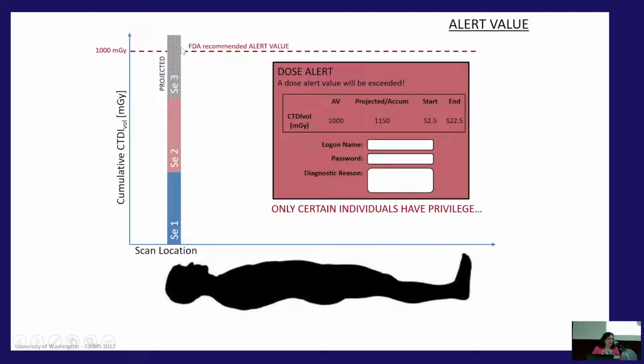If you exceed it, like in this case, your series 1, same area of the skin, series 2, same area of the skin, series 3, now you have exceeded this. It is not going to let you scan the patient. It's going to say a dose alert value will be exceeded from the scan that you have picked. You need to figure out why this is.